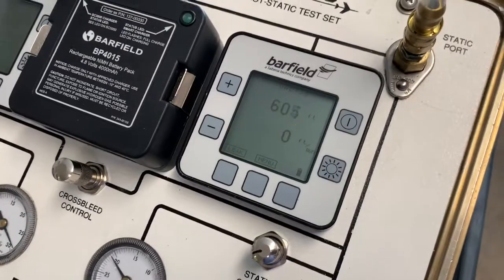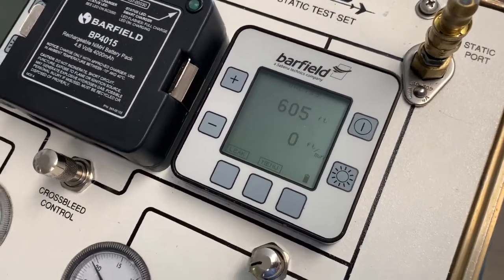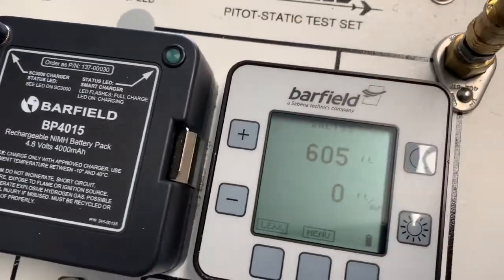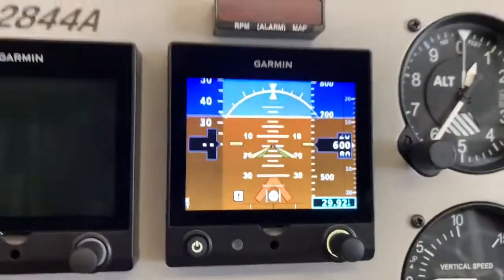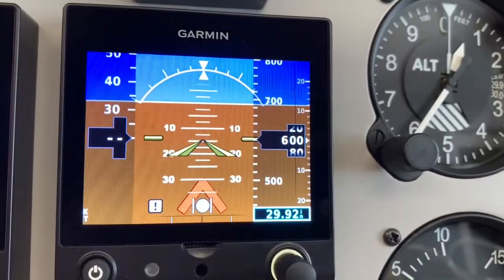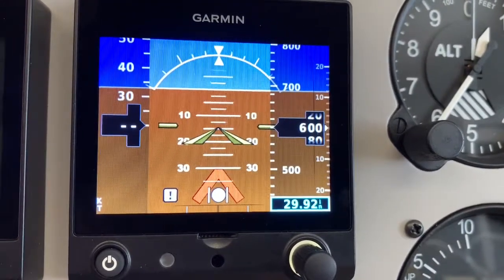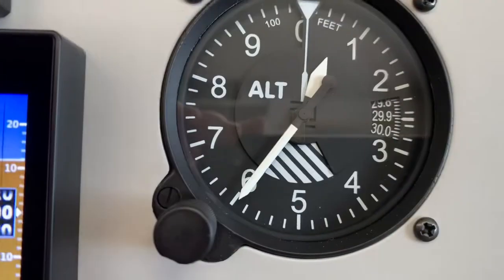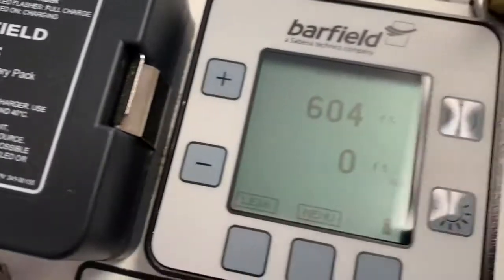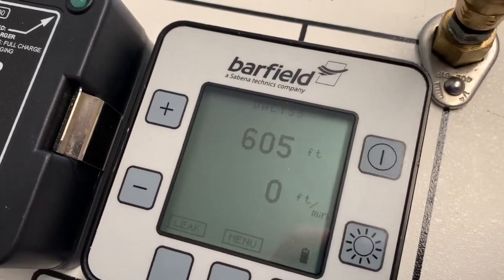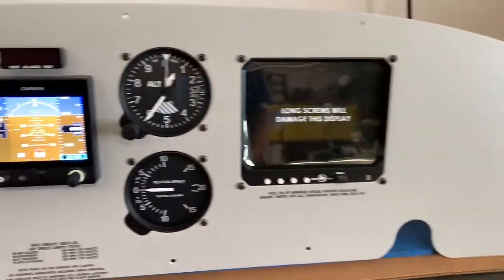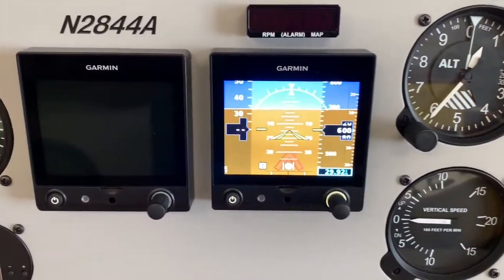Okay, we're back down to 605 feet, which is 2992. The bleed valves are open, and this is just reading field elevation. And now you'll see after going through the calibration procedure, we were considerably off to start with, and now we're reading 600 feet at 2992. Steam gauge is reading 600 feet at 2992. And our pitot-static test set is essentially reading 605 feet at 2992. So everything matches within 5 feet, and that's the way I like to set these up.